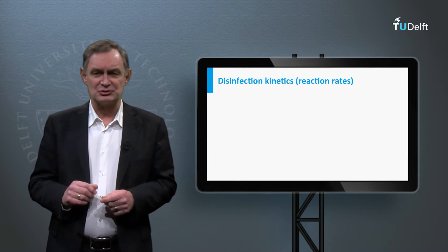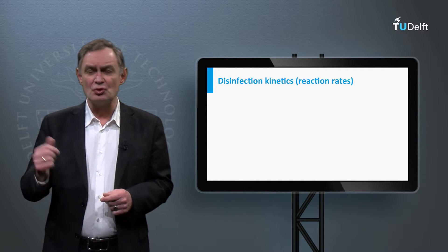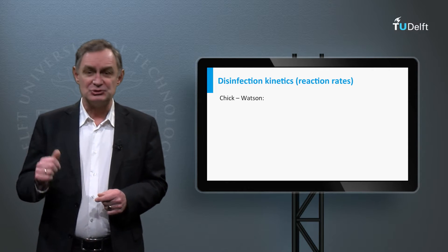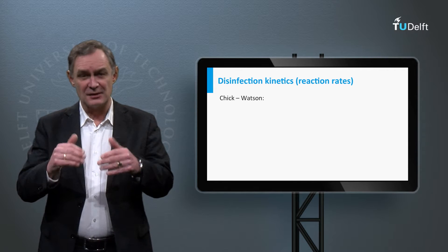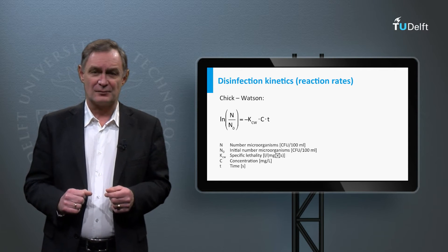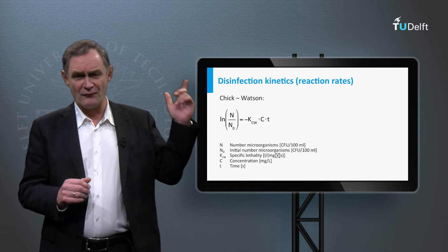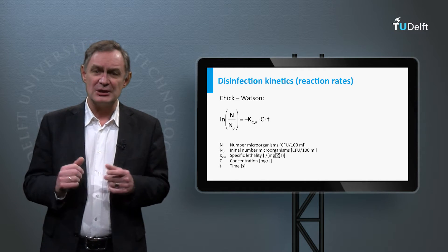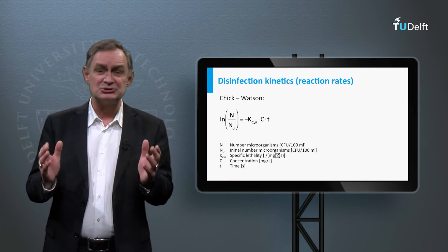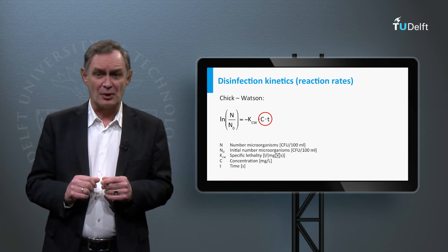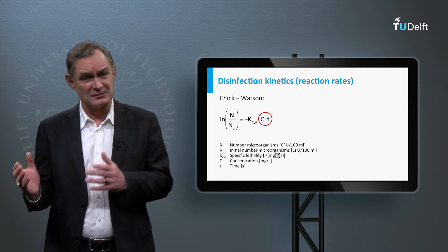Different models have been developed to describe the disinfection kinetics. The two most important are Chick's law and Watson's law. If those two are combined, the Chick-Watson equation is obtained. The natural logarithm removal of pathogens is thus assumed to be linearly proportional to the so-called CT value, which is the product of the concentration of disinfectant in the reactor and time.